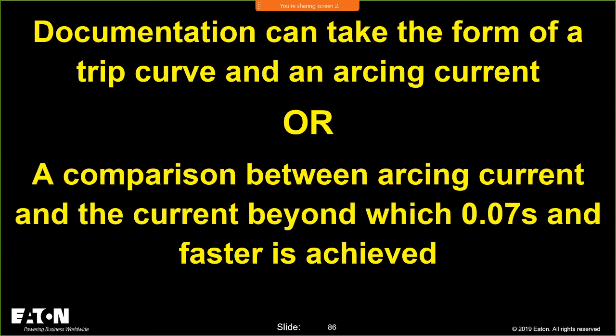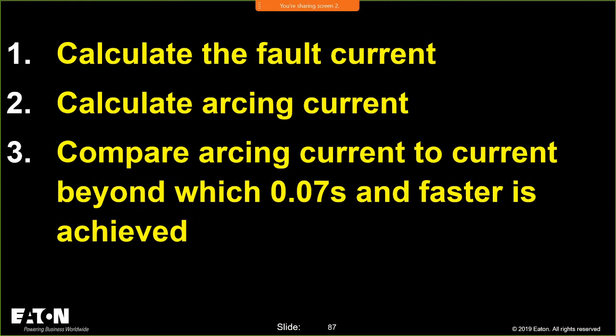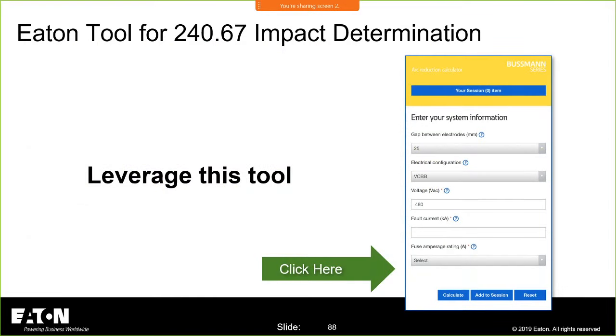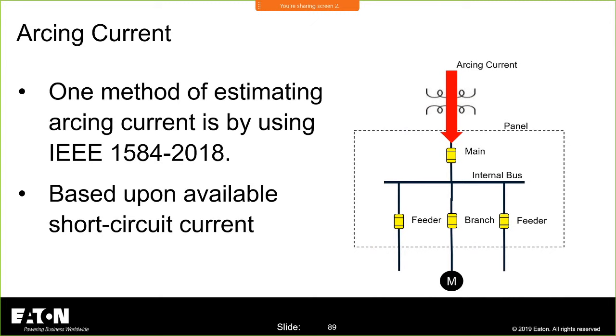Again, you could take the form of a trip curve and an arcing current, plot it on there, and give it to your inspector. You can do that comparison. You can use the tool that we have to help him understand, and we're going to have a report available with that regard. You've got to calculate the fault current, calculate the arcing current, compare those two, leverage this tool. You can get a report, email it to yourself, all that good stuff.